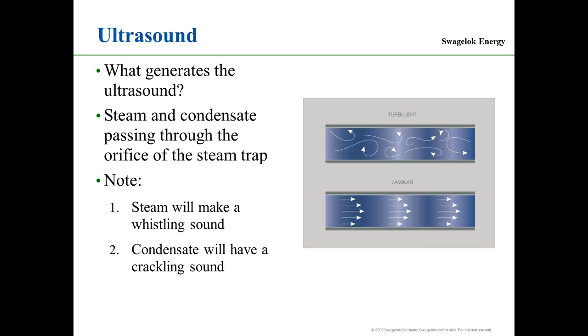And the more you listen, and the more time you're riding this bicycle using ultrasound, the more proficient you're going to be. Just putting the unit onto the steam trap and listening, your test will be instantaneous. It's a fast and easy test method. But always listen. Steam will whistle, condensate will crackle.